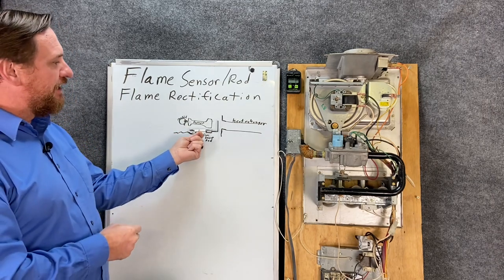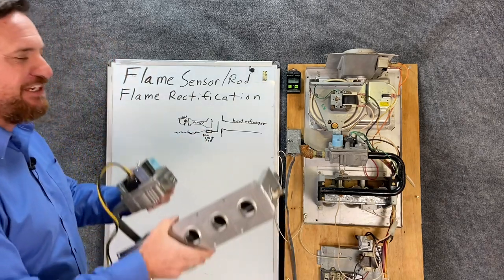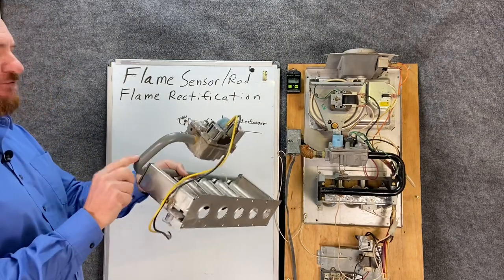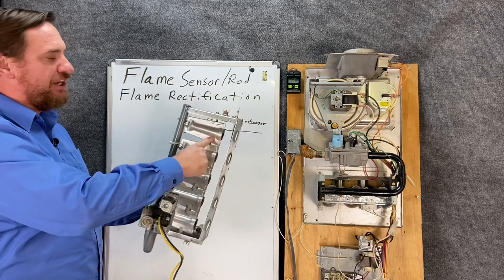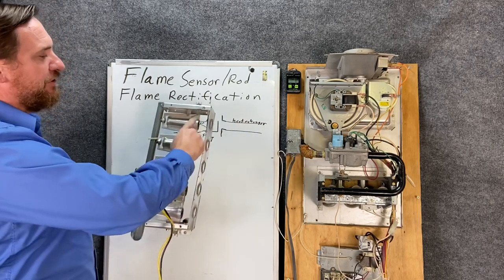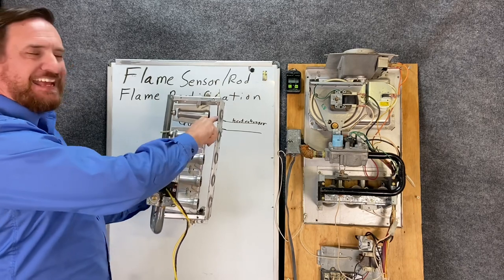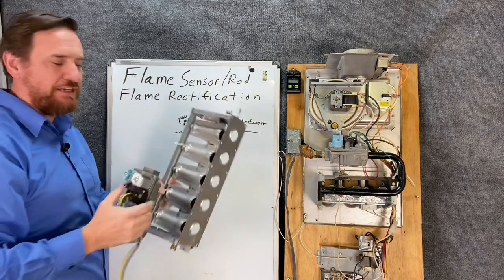So I have this really beautiful art drawing here, but let me tell you what I'm trying to draw so you understand what you're actually looking at. So here we have our manifold, and we've got our burners, in-shot burners here, and my heat exchanger would be on this side. The flame sensor is between the burners and the heat exchanger. So when I'm drawing this, this is what I'm talking about.